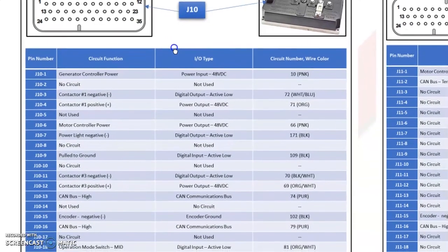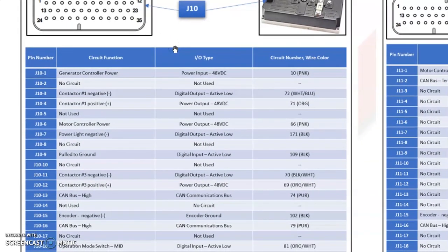So looking at each of these pins, pin number 1 is the main controller power. That's the power that we switch off and on with the relay to turn the controllers off and on. Pin number 3 is contactor number 1. That's the negative side of the contactor. Pin 4 is contactor 1 positive, so that's positive voltage to the contactor. And those are 48 volt contactors, so it is direct 48 volt DC power.